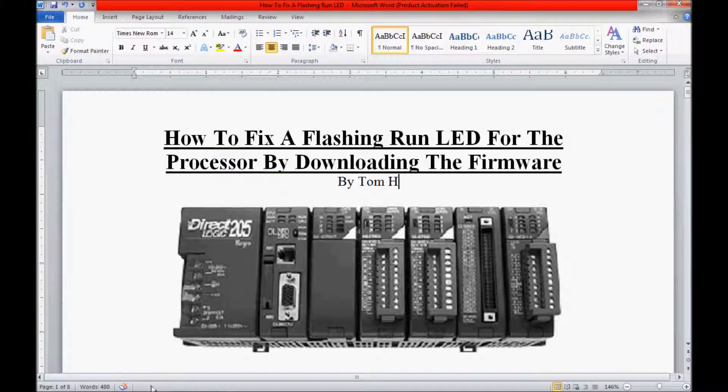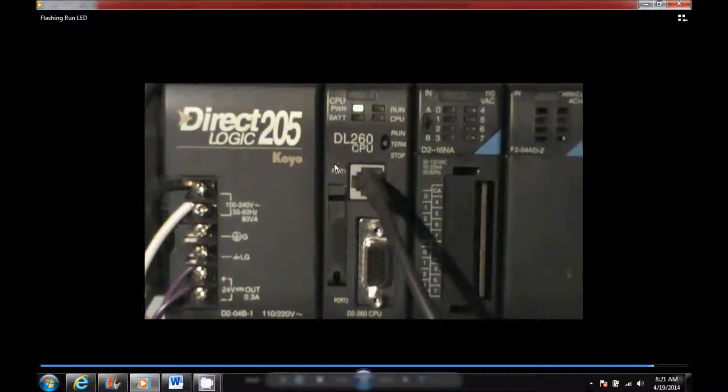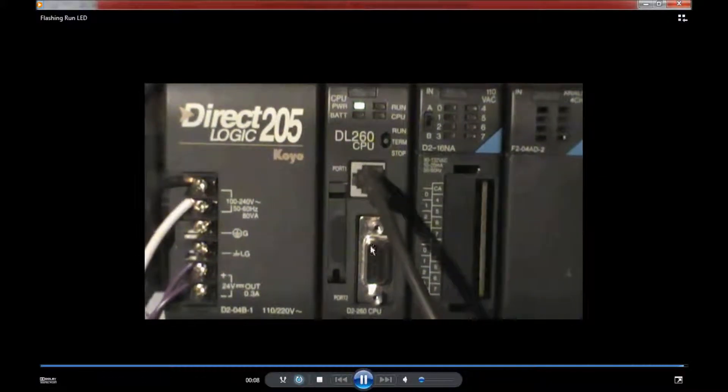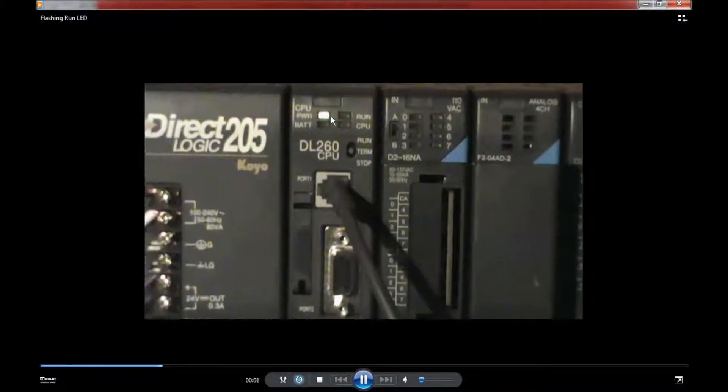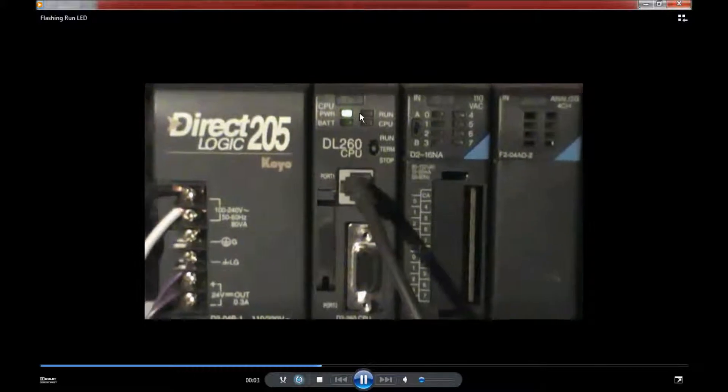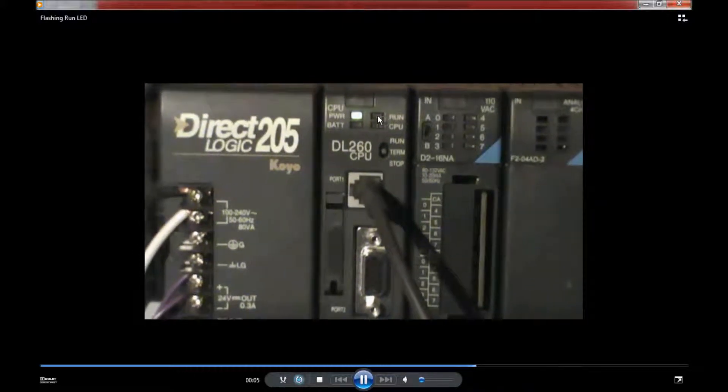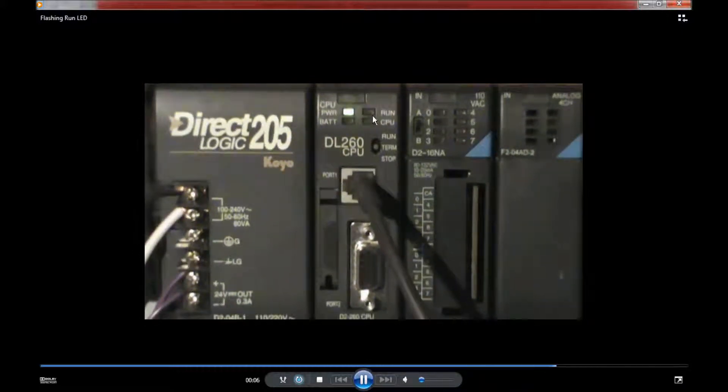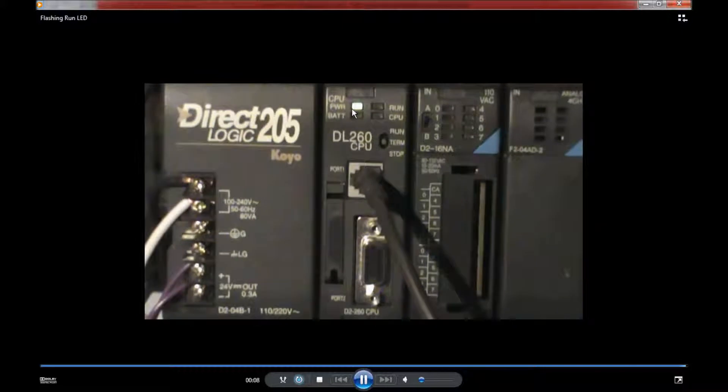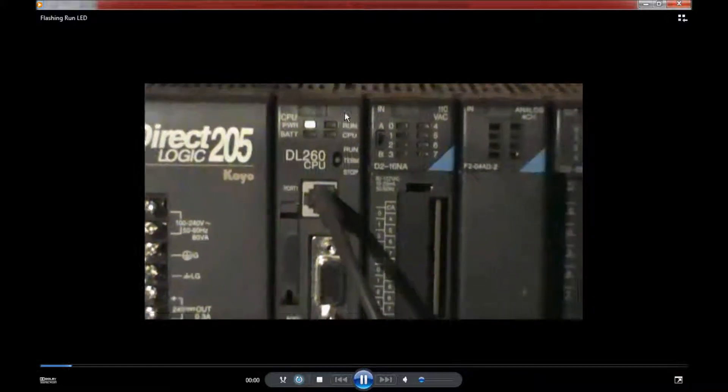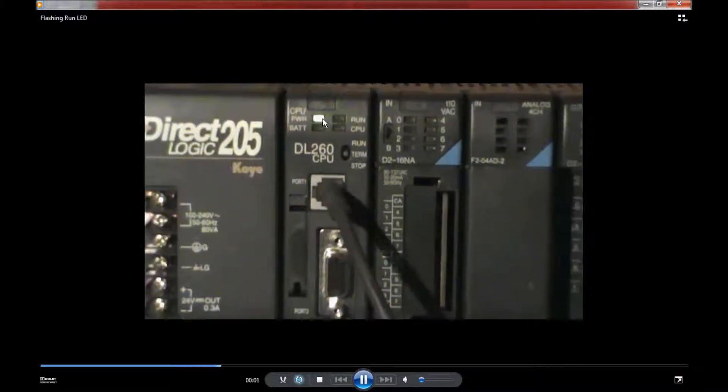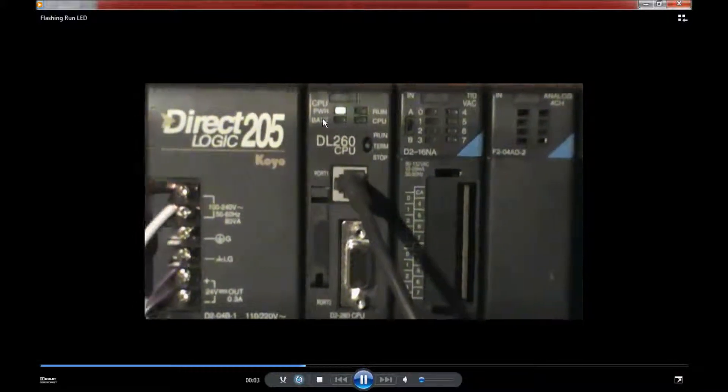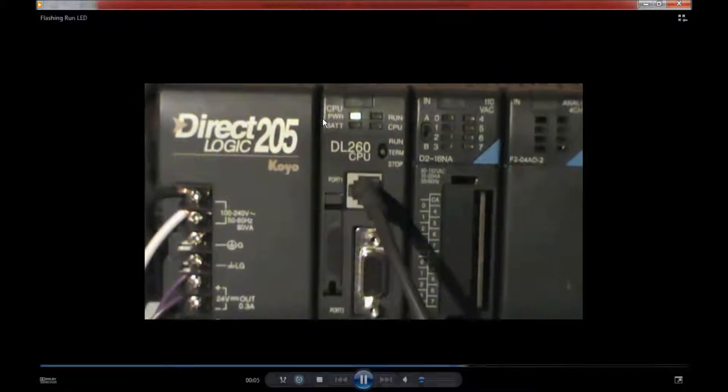I'm going to show you the problem here real quick. Here's the processor and here is the flashing LED. Now, the run LED is not supposed to flash. It's supposed to be a constant green when it's in run mode, just like the power light. I'm going to try to take care of that today.